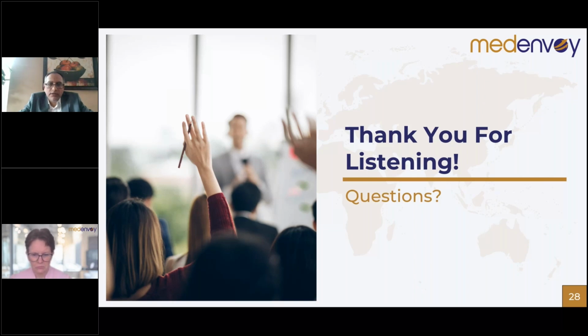Daniëlle, do you want to add something more to it? Oh, no, I think that is fully correct. And regarding the obligations under Article 10a, there needs to be an assessment of the impact of no longer having products available on the market. That's where the assessment comes from, so that we have to monitor the performance and safety of similar devices, so that we know whether there will still be products available in the market. So it also links to post-market surveillance in addition to the change management process.